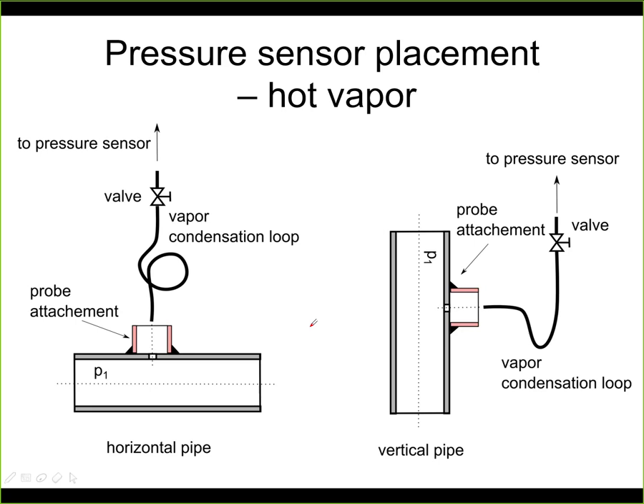If we are talking about hot vapors, we need to cool down the vapor before we connect that directly to the pressure gauge. So now this can be done in two ways. If it's a horizontal pipe, we have this probe like we've seen before, but now here we add something that's called a vapor condensation loop. And this vapor condensation loop is a loop like this of the pipe, and in this loop we give the liquid enough time to cool down, and only then it's connected to the pressure sensor.